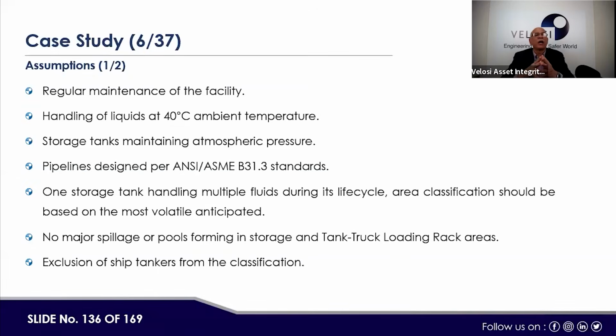Then assumptions: regular maintenance of the facilities is being done, handling of the liquid at 40°C ambient temperature is being done, storage tanks maintain atmospheric pressure, pipeline is designed as per the ASME B31.3 standard, one storage tank handles multiple fluids during its life cycle. Area classification should be based on the most volatile fluid anticipated. No major spillage or pools forming in the tank storage and tank truck area. Then exclusion of the ship tankers from the classification.